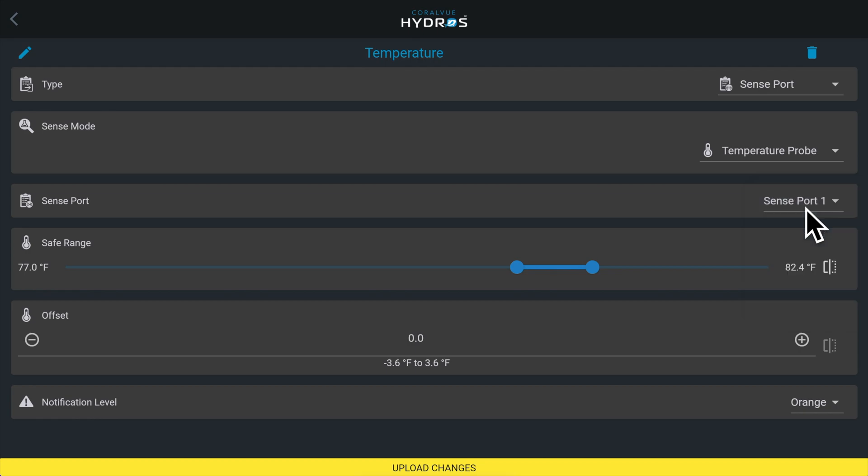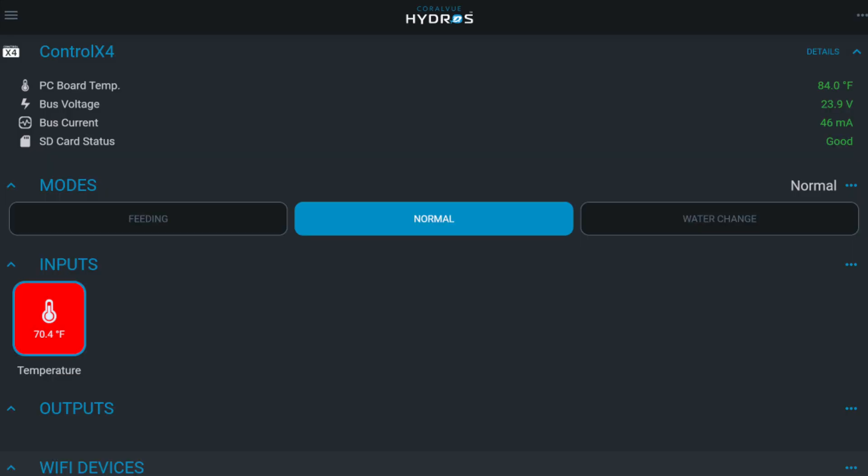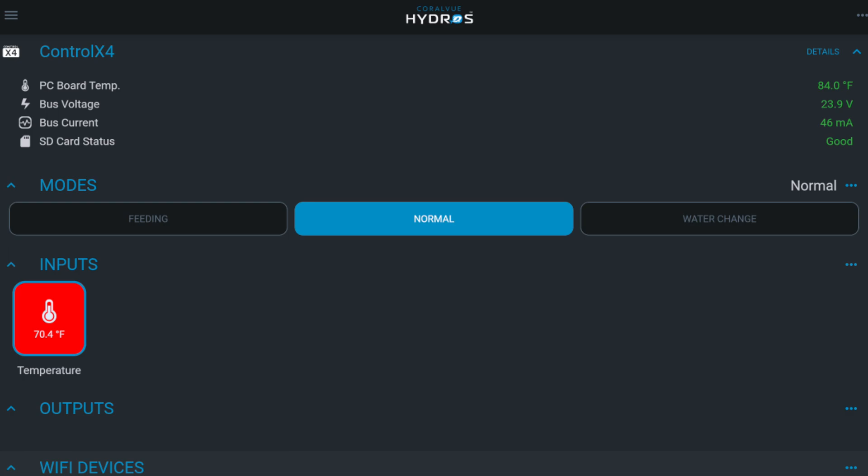Safe range low. This is your minimum temperature. If the temperature dips below this level, the input icon on the status screen will turn red and if enabled below, the controller will send out a notification. Remember, this is not the same as the low temperature when your heater turns on. Set this temperature a little lower. For example, if you keep your tank's temperature between 78 and 79 degrees, set this level to 77.5.